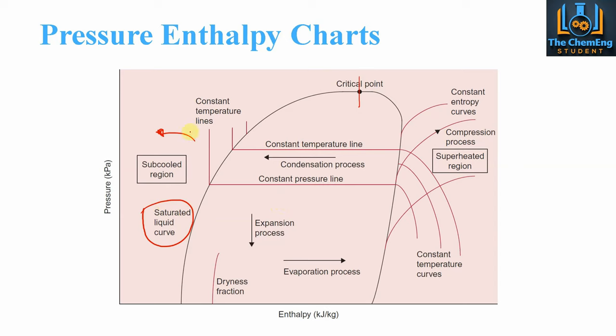For the pressure-enthalpy chart, we fix the temperature, so these lines are fixed at given temperatures. This is a simplified generic diagram — real diagrams will be shown shortly. Different temperatures are plotted at given enthalpy and pressure values, so if we know the temperature and enthalpy we can calculate the corresponding pressure, or if we know the pressure and temperature we can determine the corresponding enthalpy.